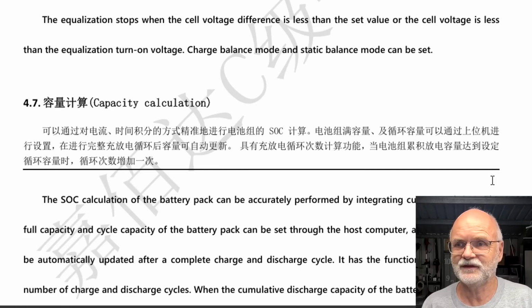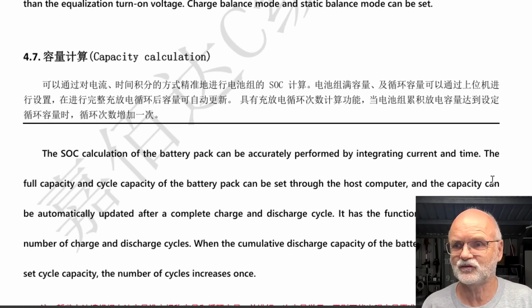The capacity calculation is described in here as well. I don't think the actual state of charge calculation is very accurate in this BMS, because it has a threshold, from what I can see, of 0.9 amps. So any current under 0.9 will result in the BMS showing 0 amps - it doesn't register smaller currents at all.